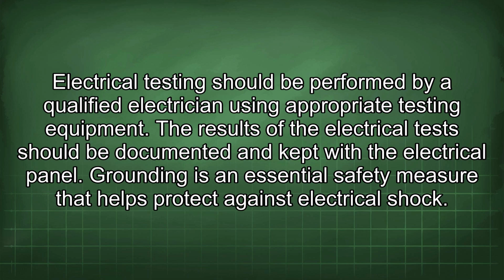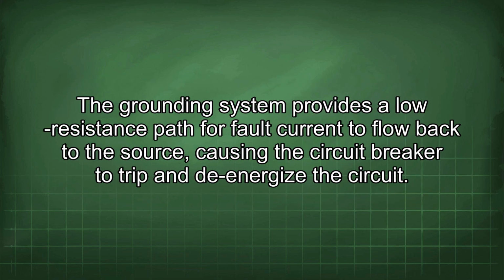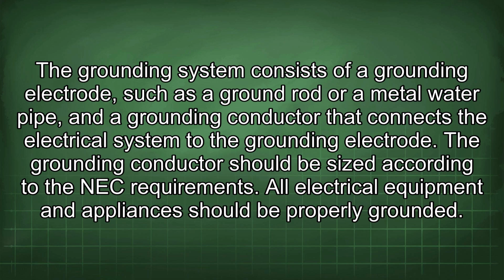Grounding is an essential safety measure that helps protect against electrical shock. The grounding system provides a low resistance path for fault current to flow back to the source, causing the circuit breaker to trip and de-energize the circuit. The grounding system consists of a grounding electrode, such as a ground rod or a metal water pipe, and a grounding conductor that connects the electrical system to the grounding electrode. The grounding conductor should be sized according to the NEC requirements.